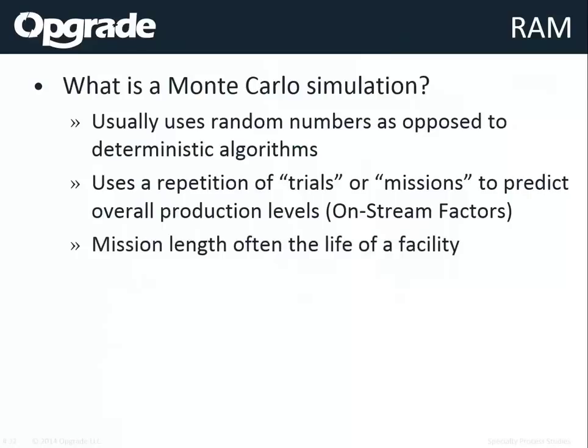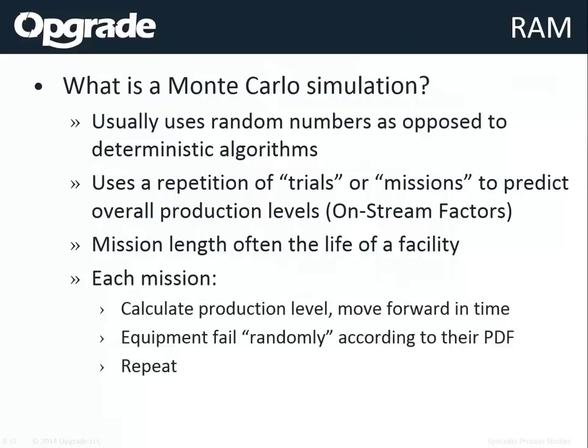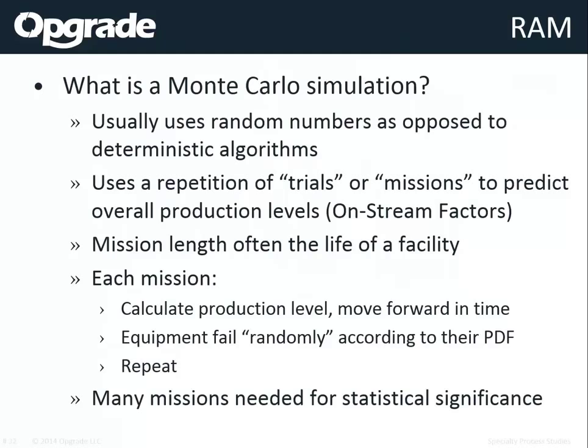The mission length is often the life cycle of the facility. The simulation calculates production, moves forward in time, causes failures based on random numbers fitted to a particular failure distribution, determines the effect on the system, calculates the production level, and moves forward in time until that item is restored or something else fails. You need many missions or trials to get a statistically significant sample size.